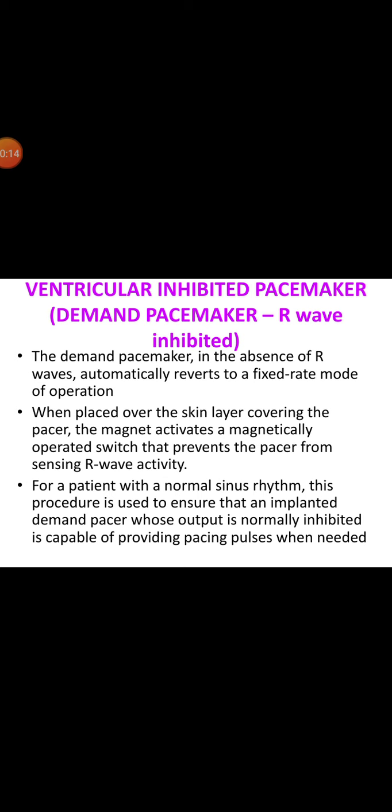The problems of shorter battery life and competition for the control of the heart led in part to the development of the ventricular programmed pulse generator. Either type of ventricular programmed pulse generator, when connected to the ventricles via electrodes, is able to sense the presence of naturally occurring R waves.